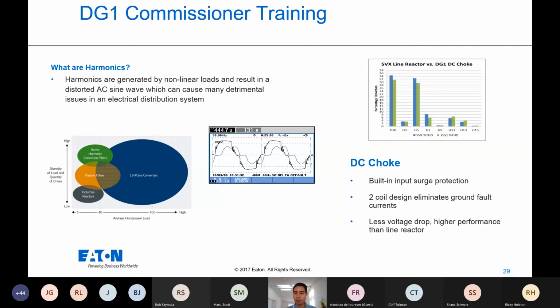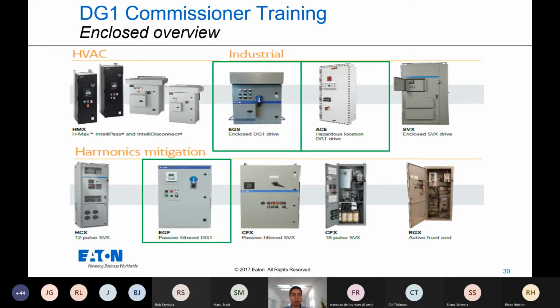It is important that you apply the correct harmonic application for your needs. And then when in doubt, the drives industry has standardized on either DC link chokes or line reactors that will reduce that power distortion from 80 to 110% down to 30%. And in order to analyze this, you should follow procedures from IEEE 519. All right, we talked about the various different drive technologies here that can help with harmonic correction at the input of the drive.